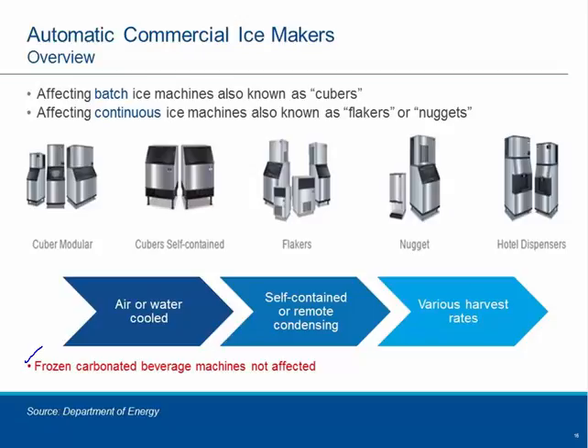I also want to point out that automatic commercial ice makers, on the EPA front, are not subject right now, as of today, to an EPA delisting, and in fact propane is available and has been SNAP listed for use. So unless these ice machines are connected to some kind of parallel rack system, they are not impacted by the EPA regulations.